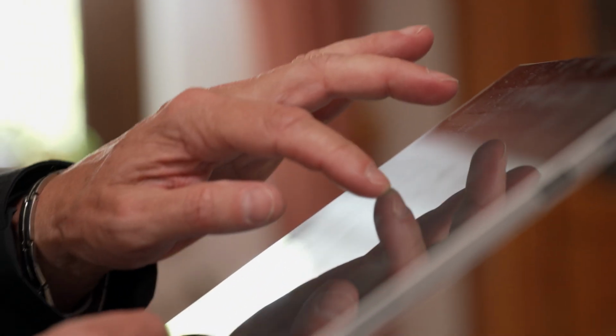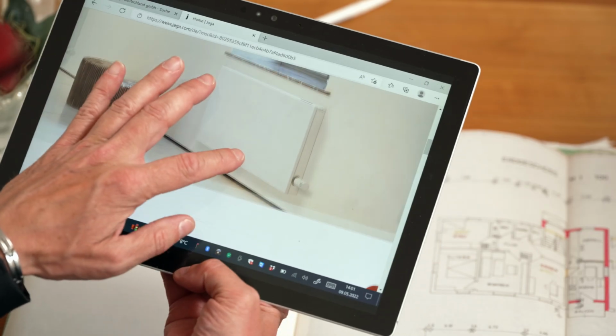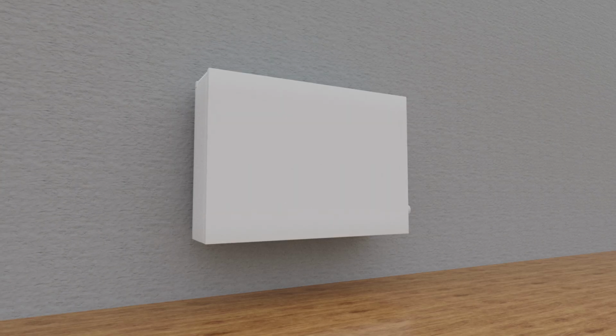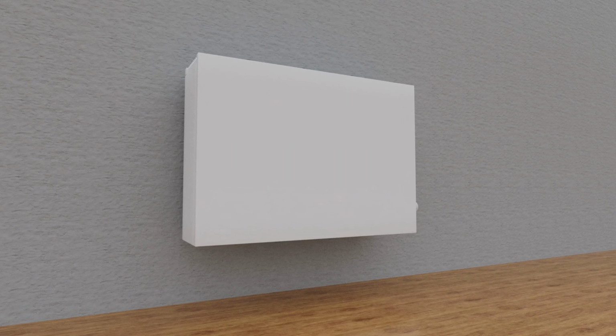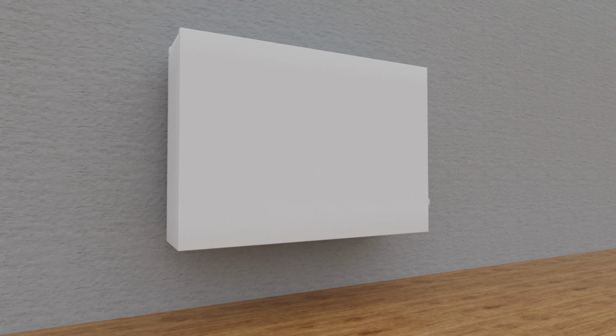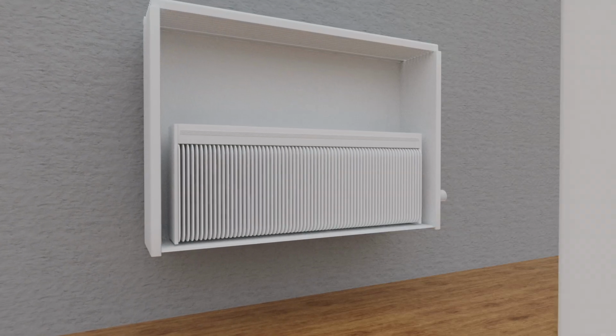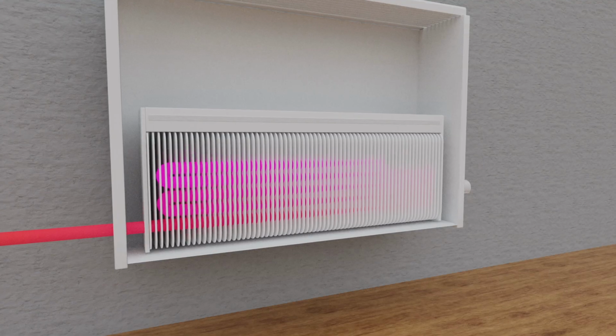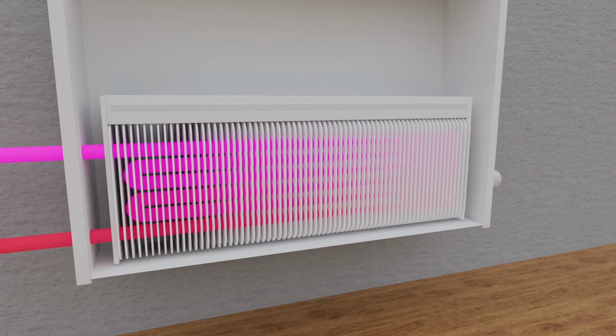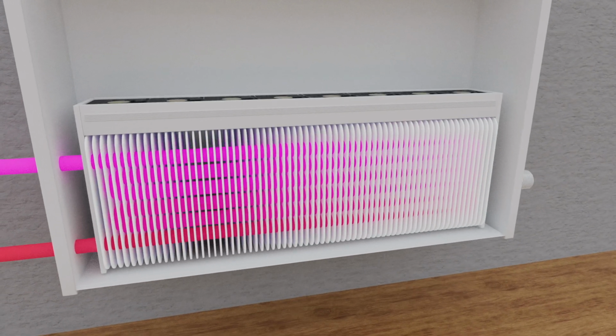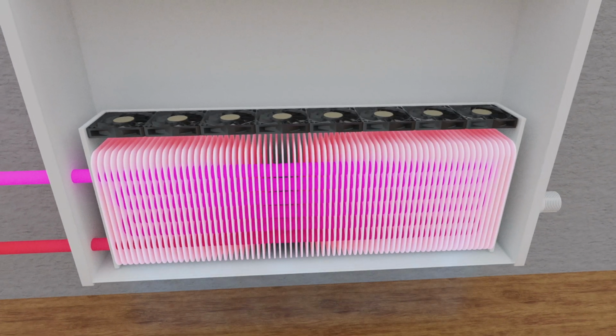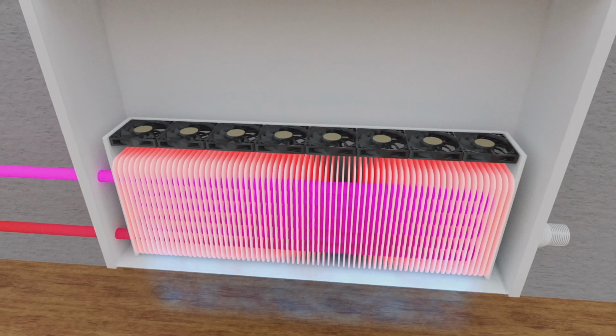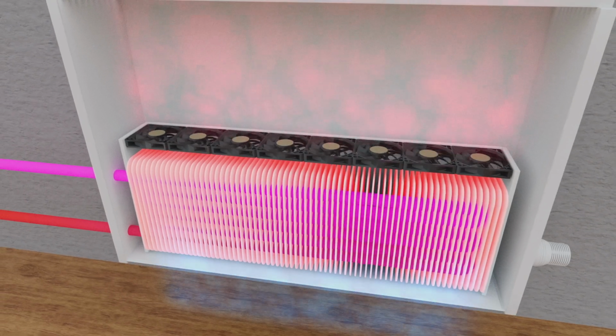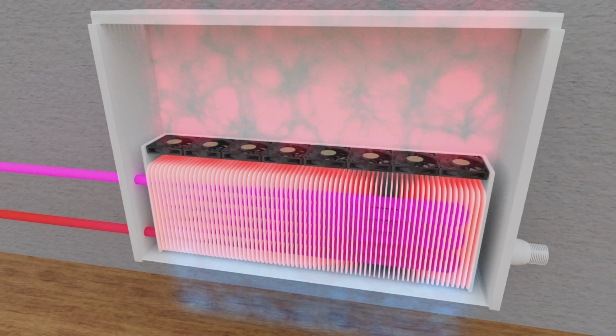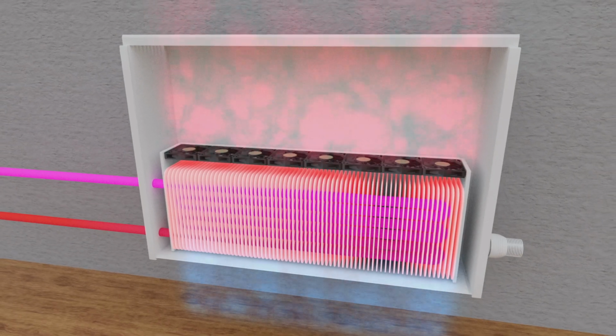If the heating capacity of the radiators isn't sufficient, and homeowners wish to avoid expensive installation of underfloor heating, so-called low-temperature radiators are an alternative. These are radiators through which the heating water flows. Above them is a row of small fans that suck air through the fins. This airflow increases the heat exchange compared to the normal radiator. As a result, the overall heating temperature can be lowered.